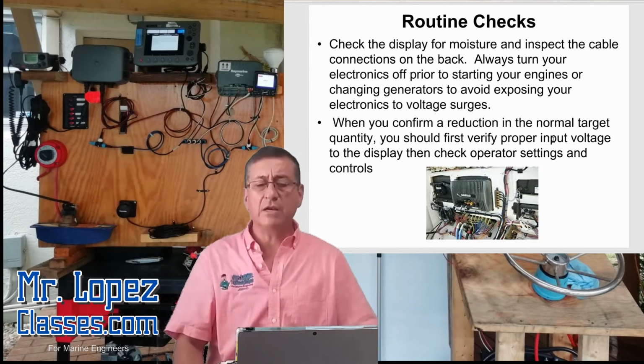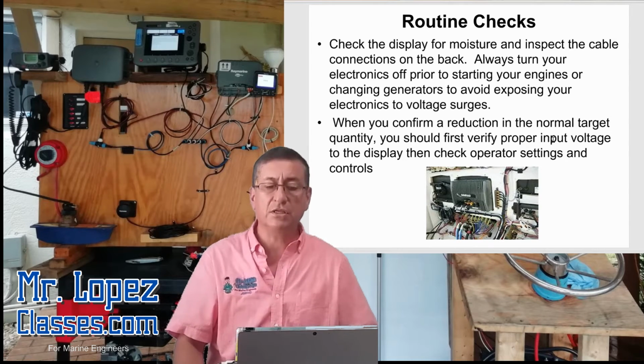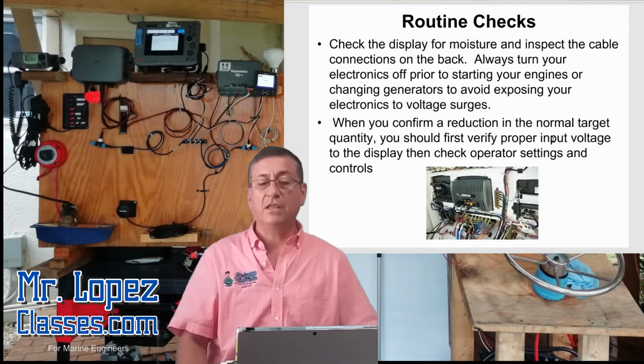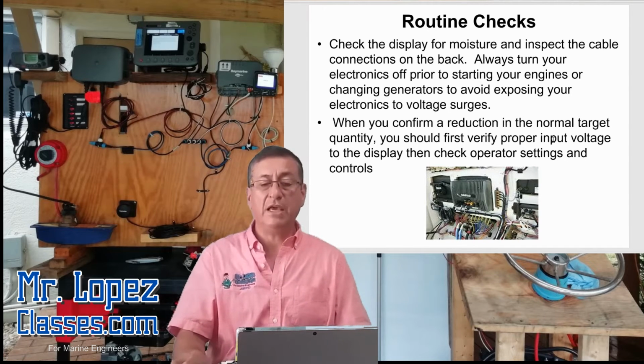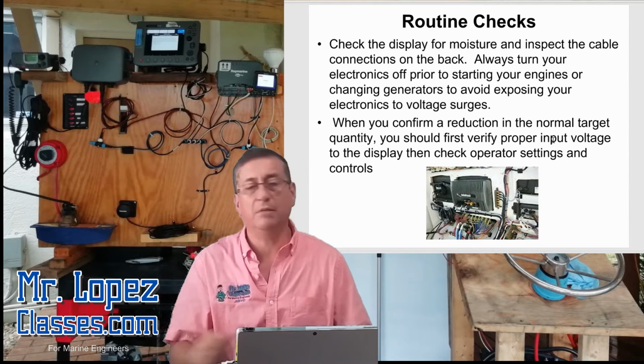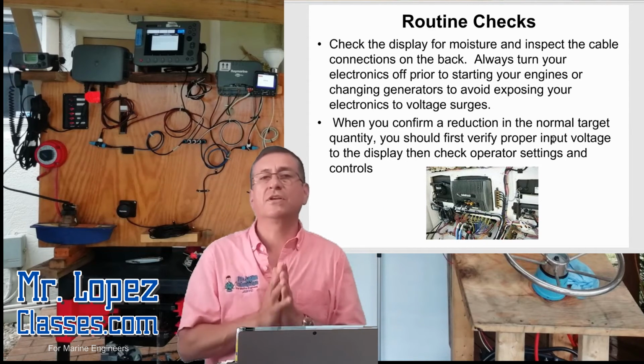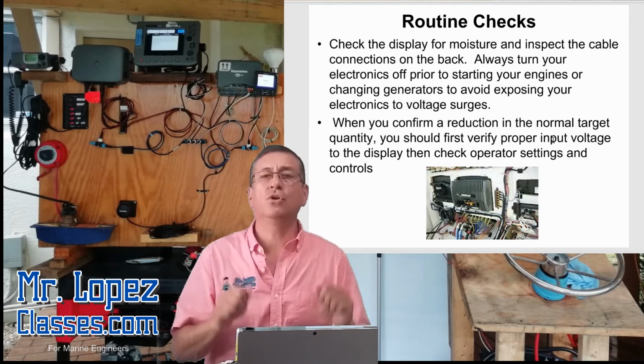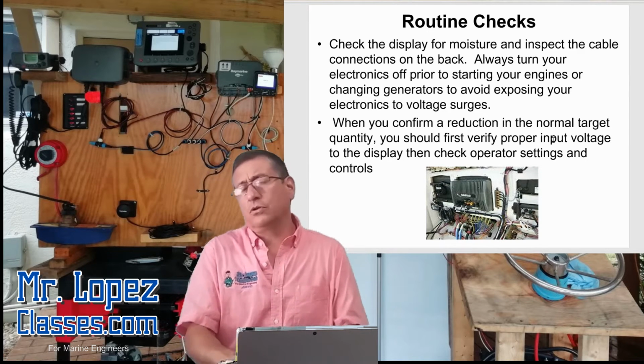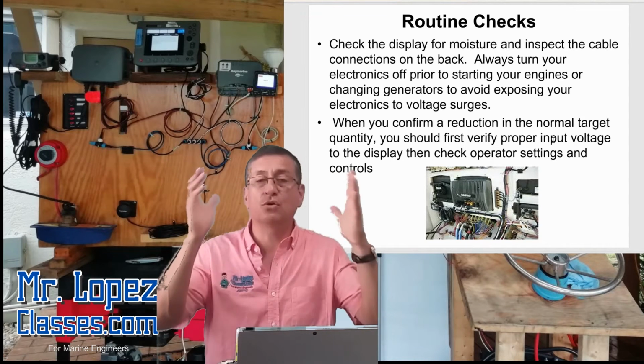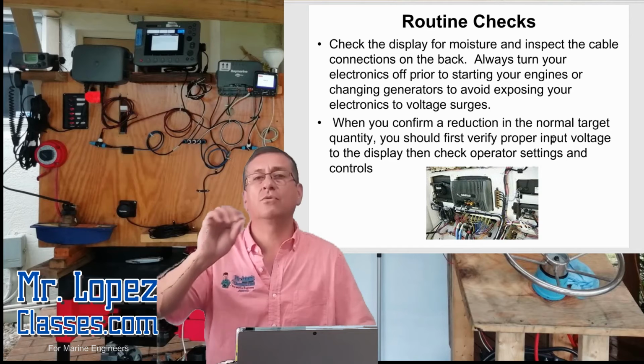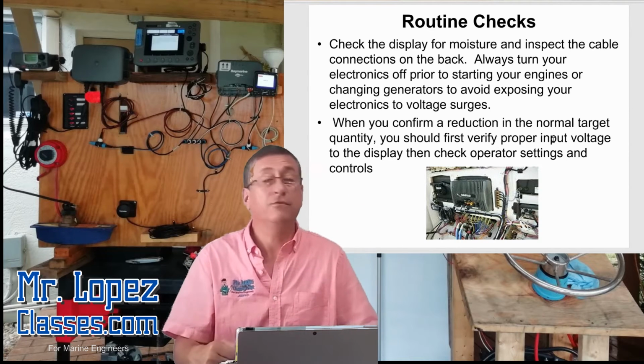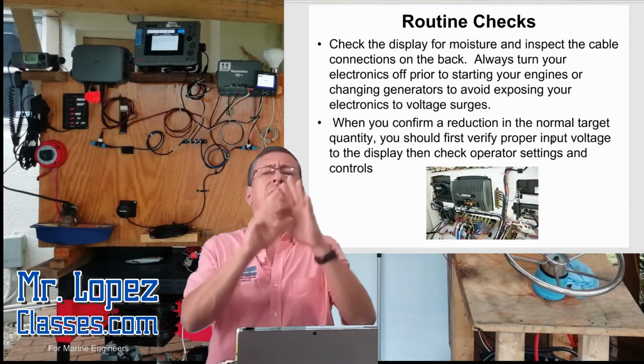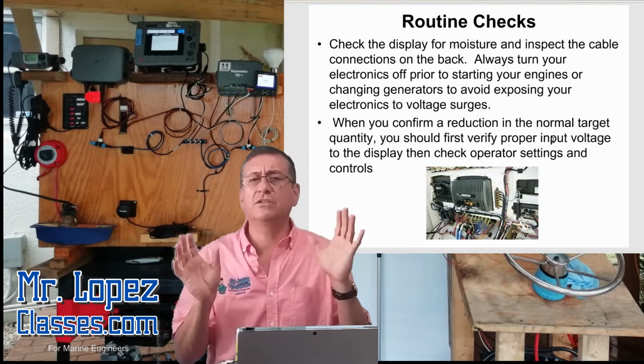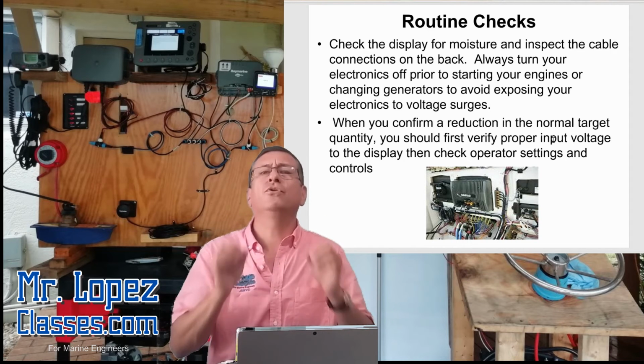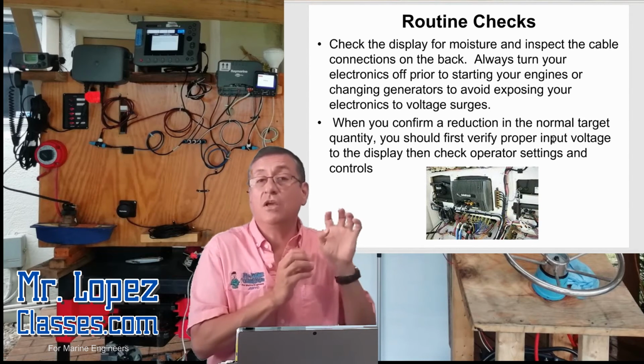Okay, when you confirm a reduction in the normal target, you should verify the proper input voltage on the display and verify the ground. The ground is, in my opinion, the cause of 99% of the problems. Bad ground, contaminated ground, loose ground, improperly grounded. And of course, fuses, because for some reason the power increased suddenly past the limit and the fuse is blown. The fuse is an important element. Never install in electrical or electronic circuits an equipment without the fuse. The fuse is according to the capacity of the equipment.